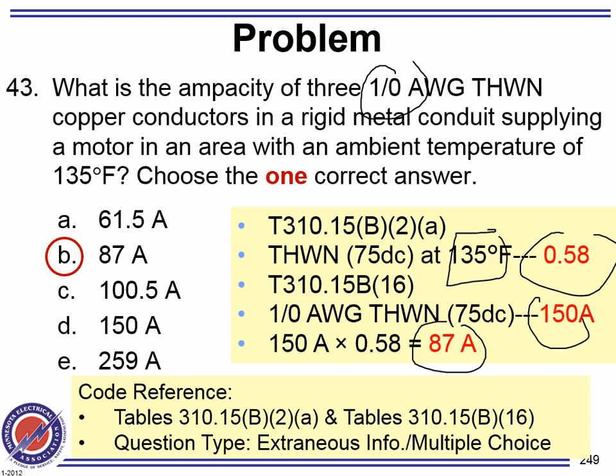If motors are continuous load, under normal operating condition, how much current can this conductor give you? 150, right? Because it's a motor and the conductor 1/0 is larger than number 1. Now, if it's feeding a motor, remember, it's limited to 80%. That's the reciprocal of 1.25. So 0.8 times 150 is 120. Now I can't pull more than 120 out of it.